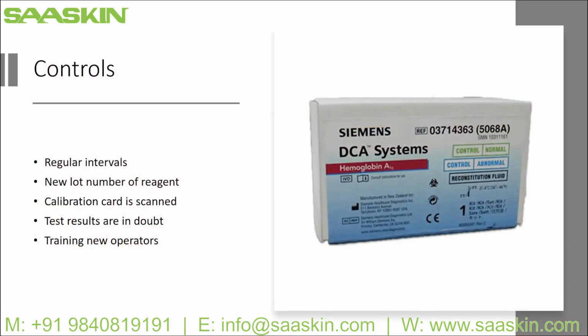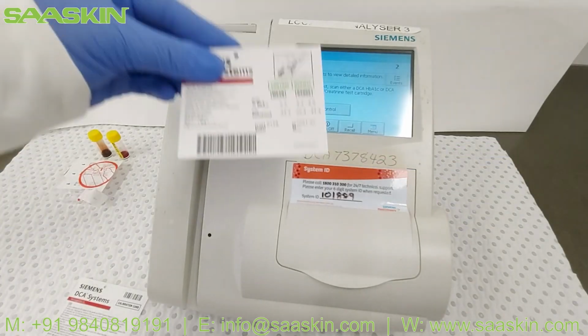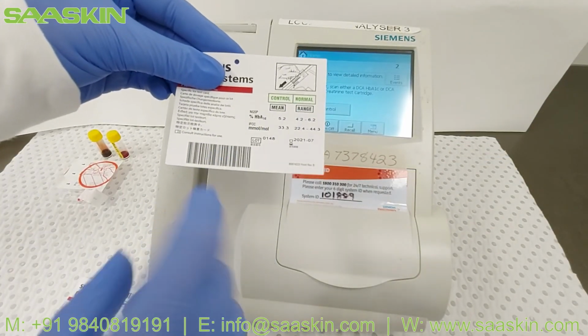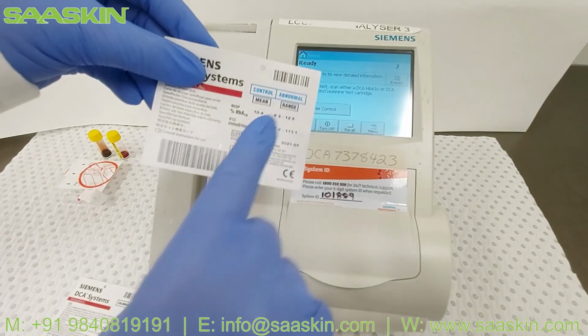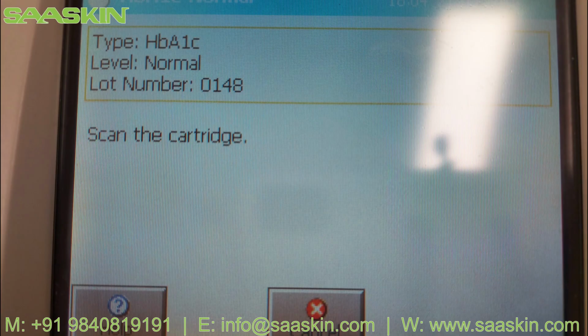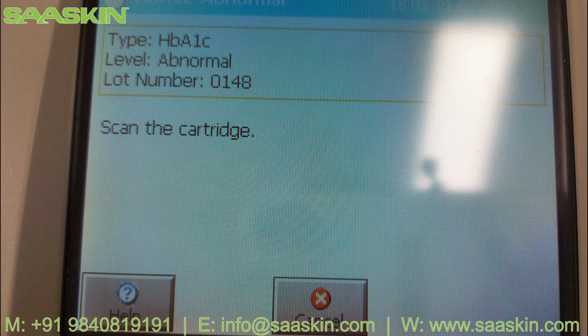To ensure the sample result is accurate, normal and abnormal controls need to also be run. The procedure for running controls is the same as patient samples. Before running controls, the control card barcode for the control that you intend on loading needs to be scanned, so that Vantage recognises and calculates the acceptance criteria for the correct control lot number.